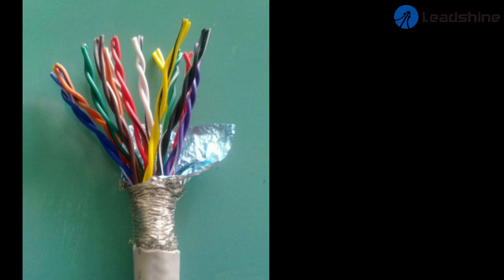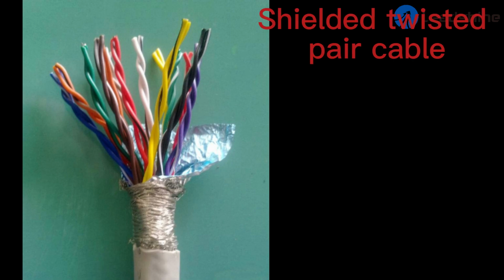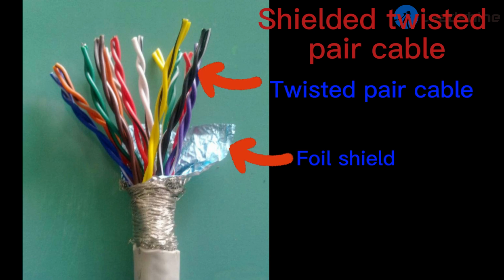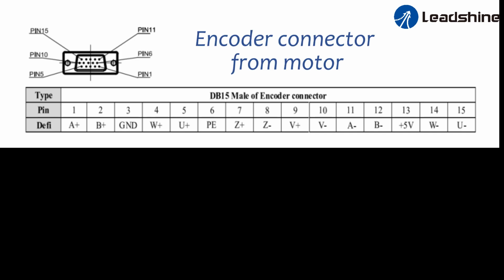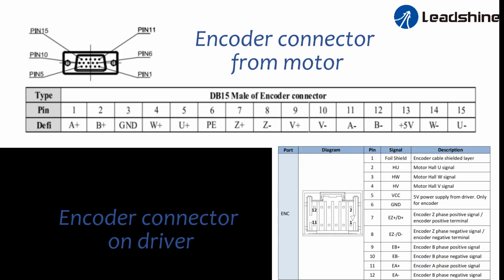First, according to the definition of driver and motor encoder interface, connect the encoder cable. To prevent electromagnetic interference, the encoder cable is recommended to use shielded cable. This graph shows the signal definition of the encoder. And this graph shows the encoder terminal of the driver. Connect the encoder cable and motor cable according to the definition.